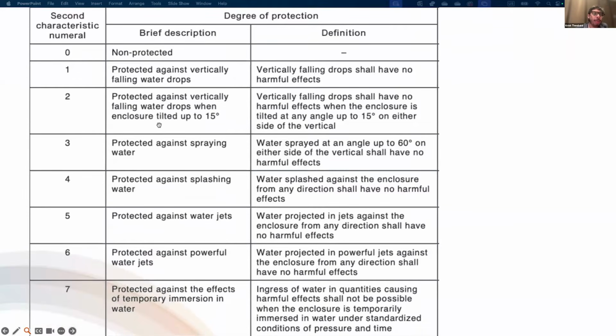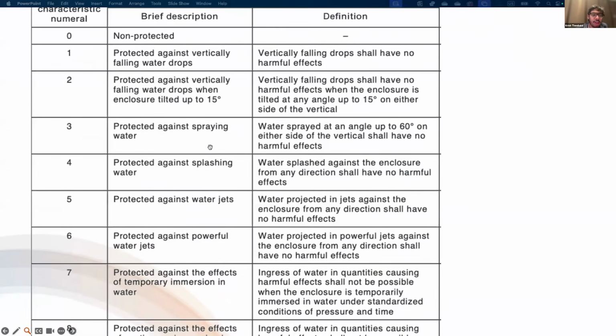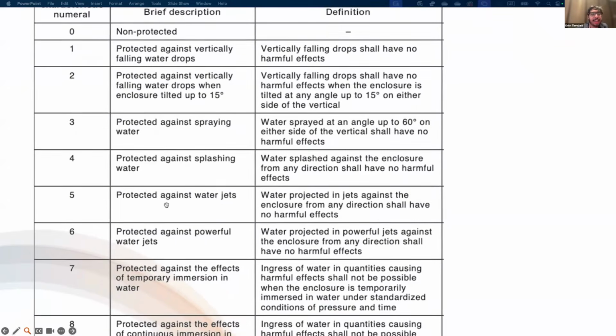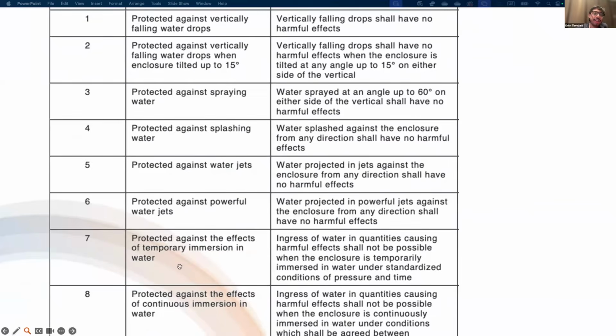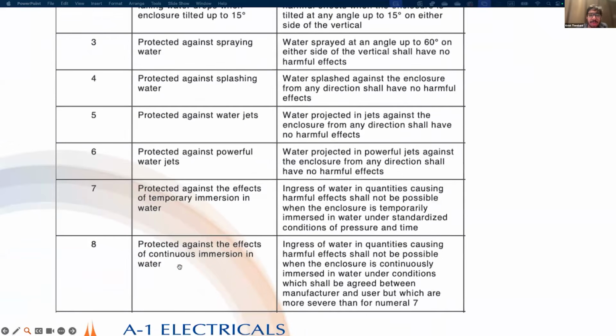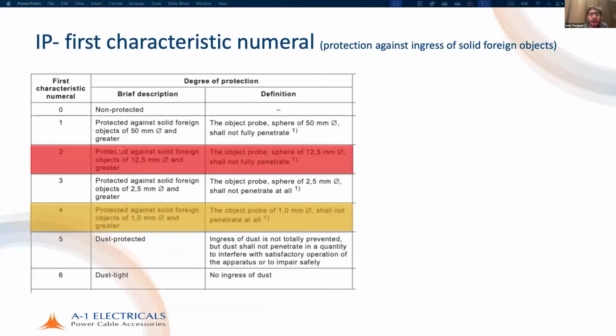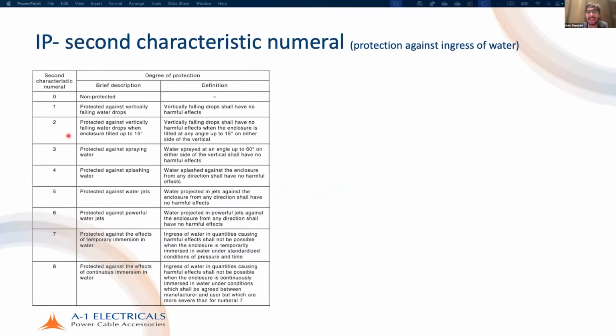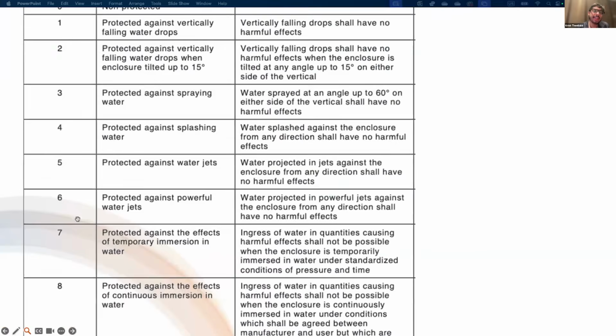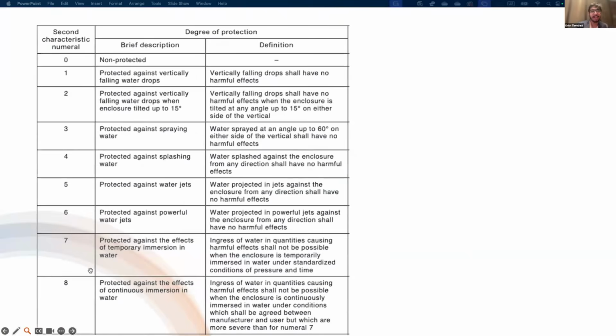Protected against vertically falling water drops when an enclosure is tilted up to 15 degrees. Protected against spraying water is 3, 4 is protected against splashing water, 5 is jets, 6 is powerful water jets, 7 is effects of temporary immersion, and 8 is effects of continuous immersion. The important thing is, when there is a certain characteristic numeral designated, all the lower ones are also considered as satisfied for the first characteristic numeral, so protection against ingress of solid foreign objects and access to hazardous parts. But for the second characteristic numeral, up to 6, it means that all the previous are taken into account. After 7, it is different. It needs to be verified on a case by case basis.